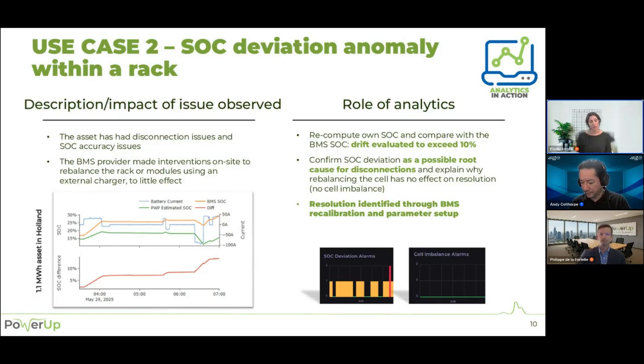Clearly, what does that mean for the user? In this case, the BESS is used by a customer that has its systems co-located with EV chargers. So if the SOC value given by the BMS is higher than the real SOC, what can happen is that the EMS might say it's okay, you can still do a fast charging there.